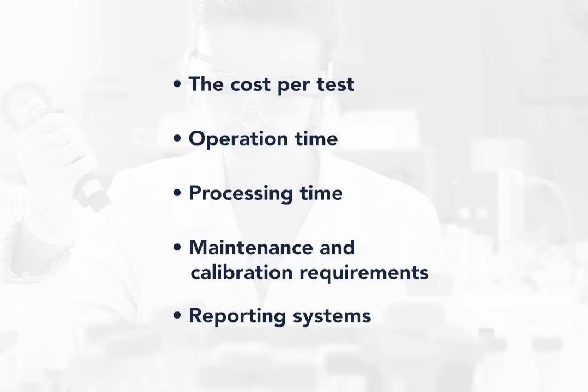But that's not all. It is a common practice to substitute reagents manufactured by another company that are compatible with the instrument as a way of saving money and lowering the cost per test. Of course, this is predicated on validation studies allowing this.